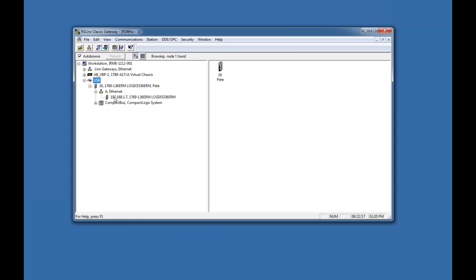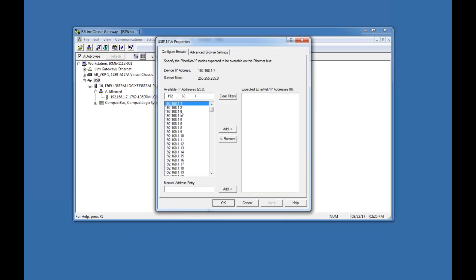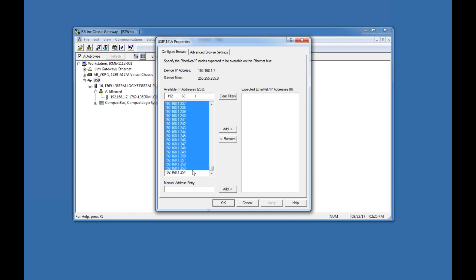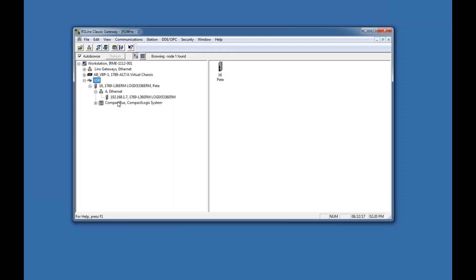Right now nothing is showing up. What you need to do is turn your PLC into a bridge — it often already defaults to that. Right-click on Ethernet and go to Properties. This allows you to search for any IP address through the USB connected to the PLC by Ethernet. I'll scroll down, hold Shift, highlight everything, add it to the side, hit Apply and OK, and wait for it to browse.